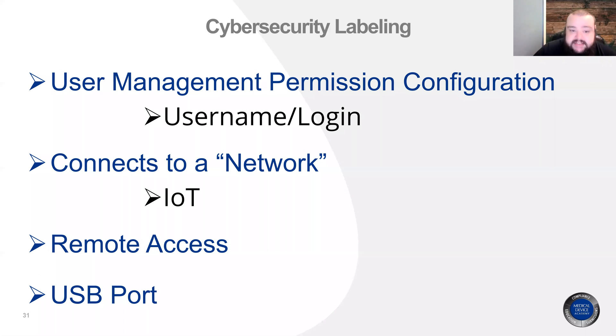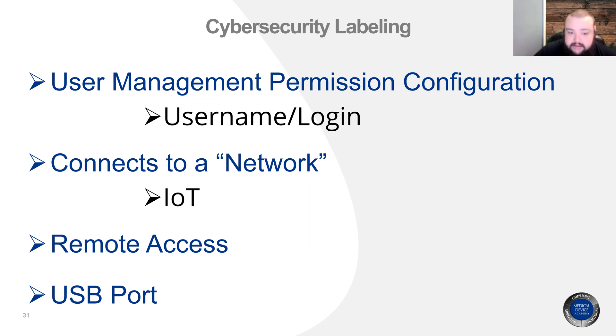When you ask yourself whether your device has a cybersecurity risk, you can ask a handful of questions — it's usually pretty easy to figure out. Does your device have user management permission configuration, users and admin-level permissions, or something as simple as a username and login? Does it connect to a network, or is it part of the internet of things? Can it be accessed remotely, or does it have a USB port?